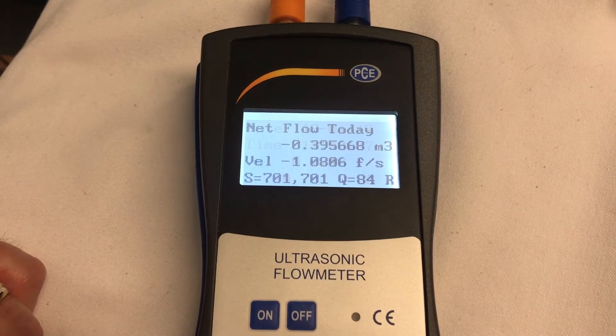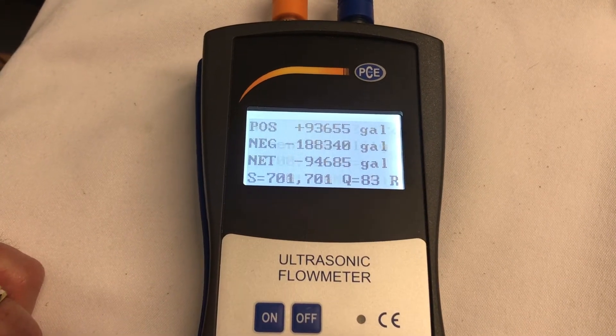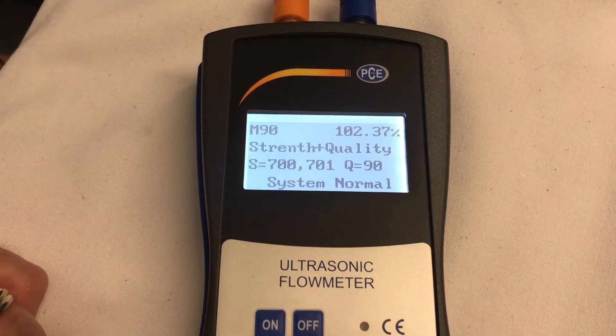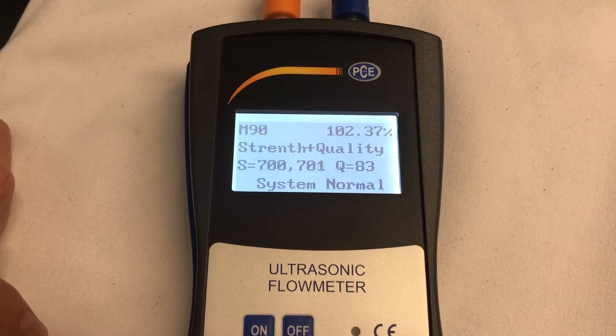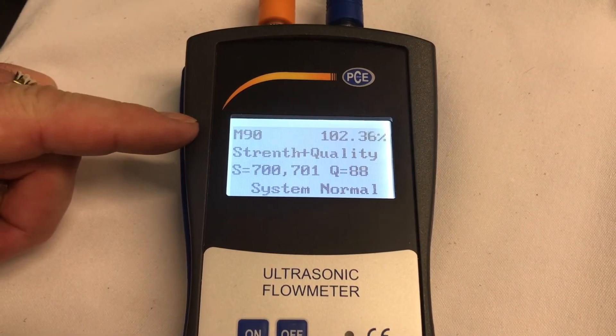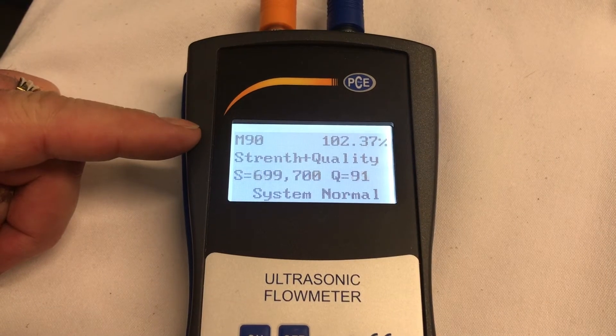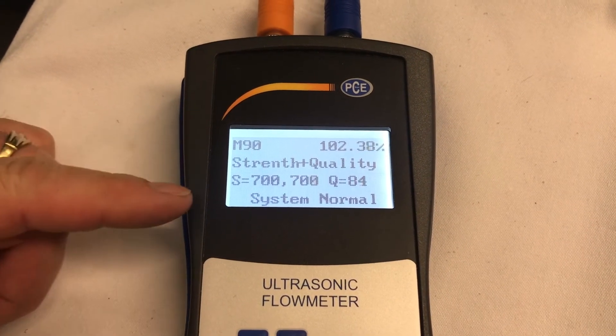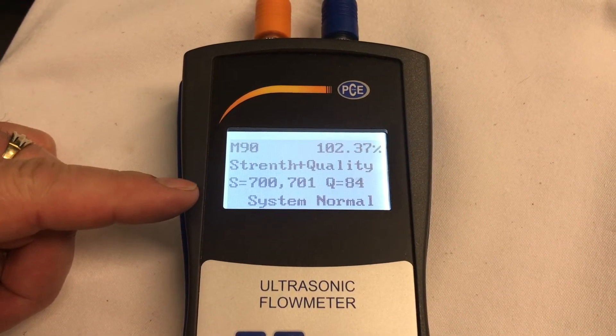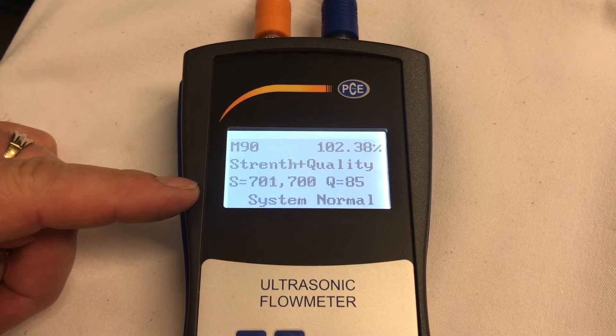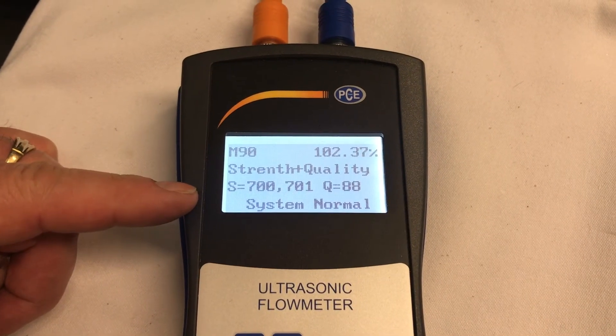Next, we get to M-90, which is time constant. The time constant on M-90 has to be 100%. And the signal strength is greater than 700. And the signal quality is greater than 60.